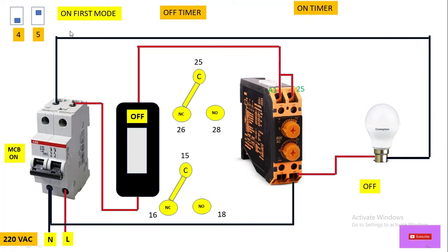Now let's move to on first mode. To set this cyclic timer in on first mode, we have to shift the number 4 DIP switch to the upside and the number 5 DIP switch to the downside. Now we have set this timer in on first mode.